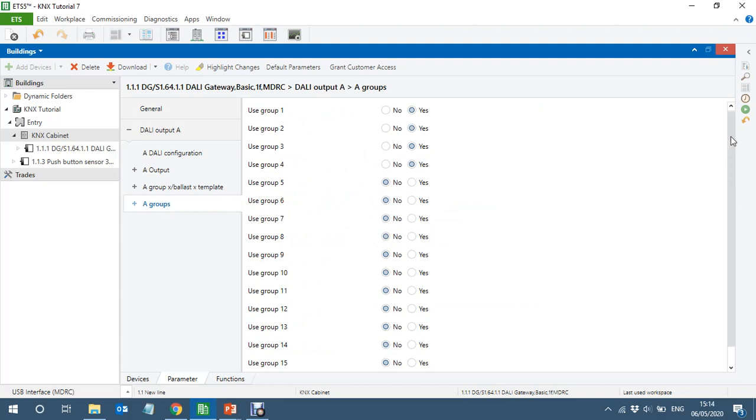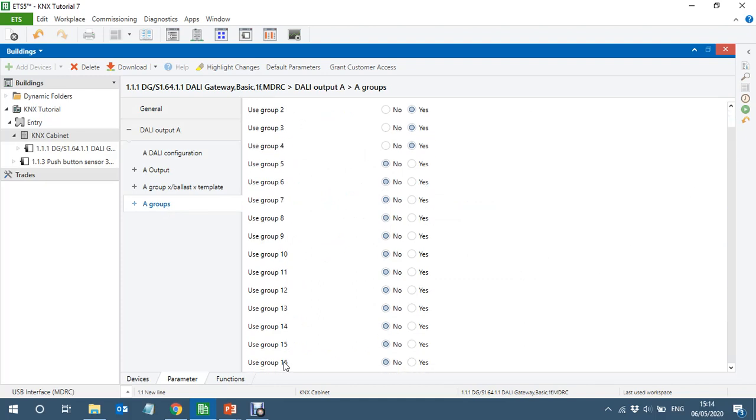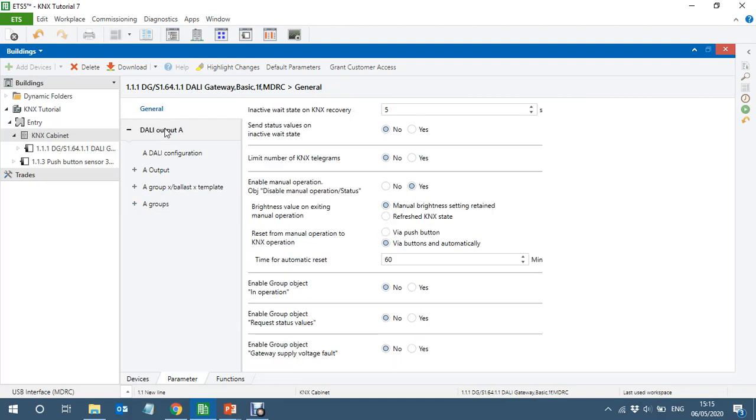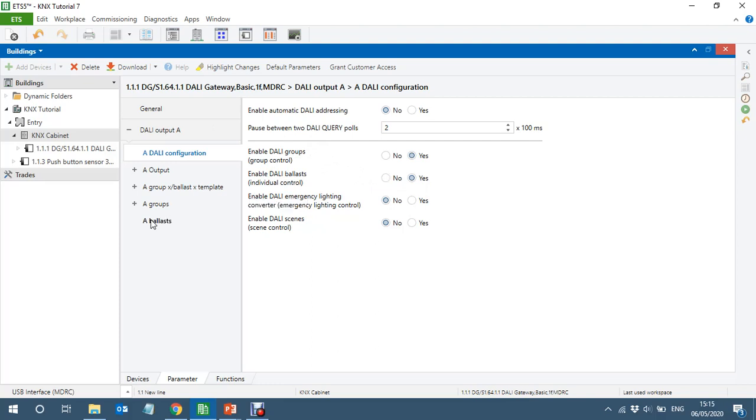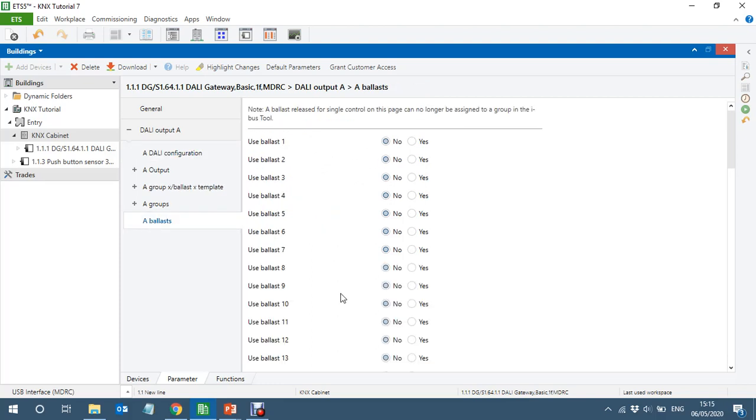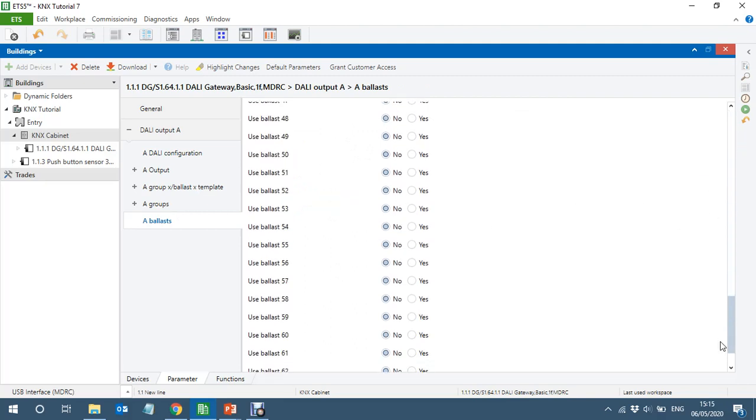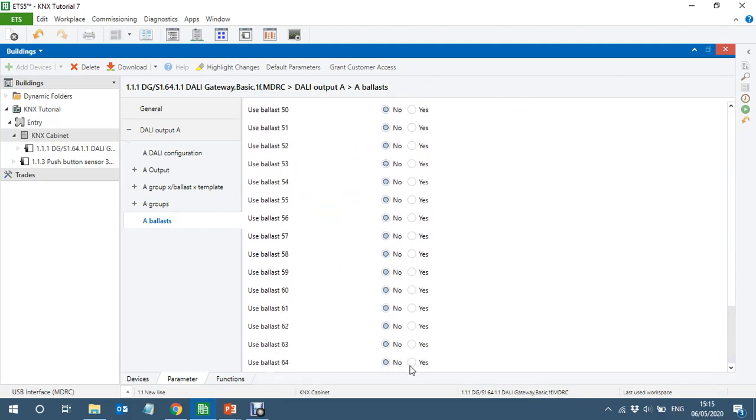16 groups are a lot of groups, so I'm sure they are mostly enough. But in case in the 16 groups you will have to control all the 64 lights groups. Now if in case you need more groups than 16, then you can go to general, I think, DALI output. So you can enable DALI ballast individual control as well. If I enable here, you can see the ballast as well, so you can control all the 64 ballast individually as well if I want.